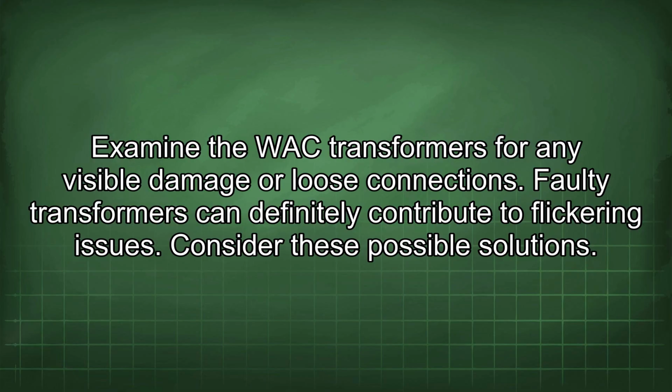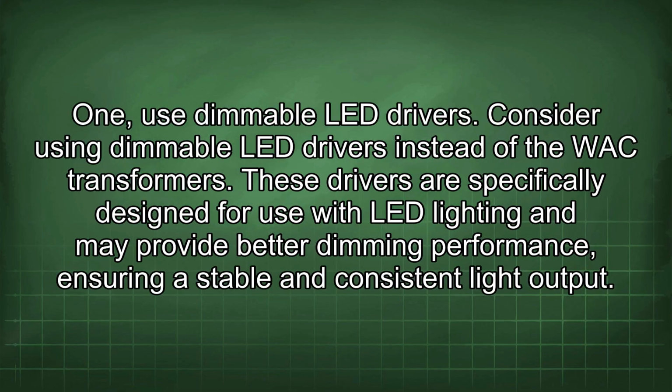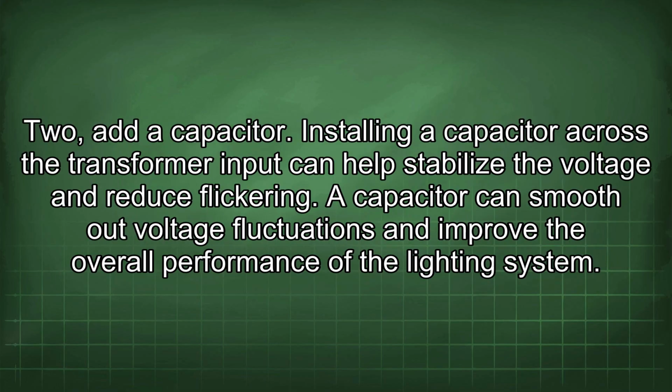Consider these possible solutions. 1. Use dimmable LED drivers. Consider using dimmable LED drivers instead of the WAC transformers. These drivers are specifically designed for use with LED lighting and may provide better dimming performance, ensuring a stable and consistent light output.